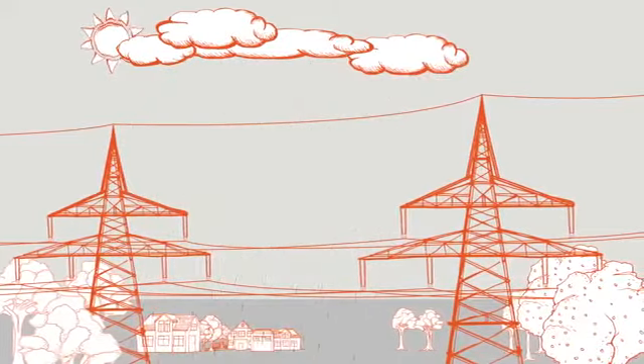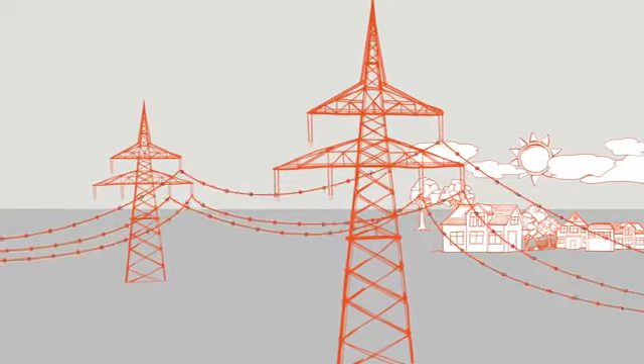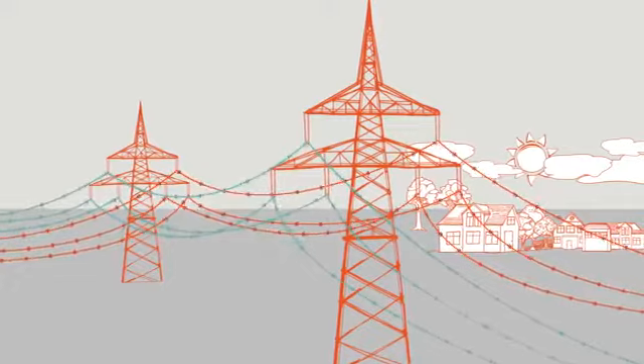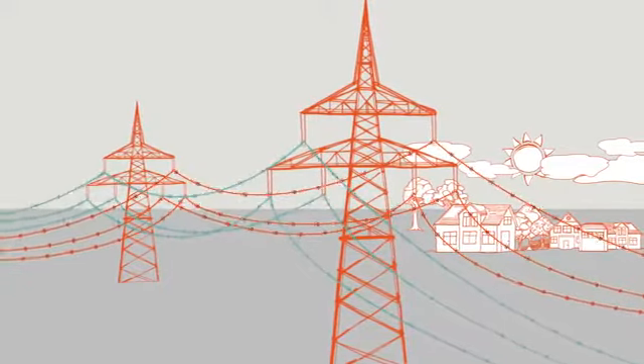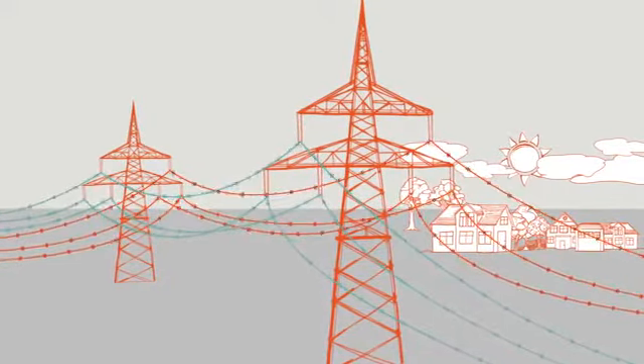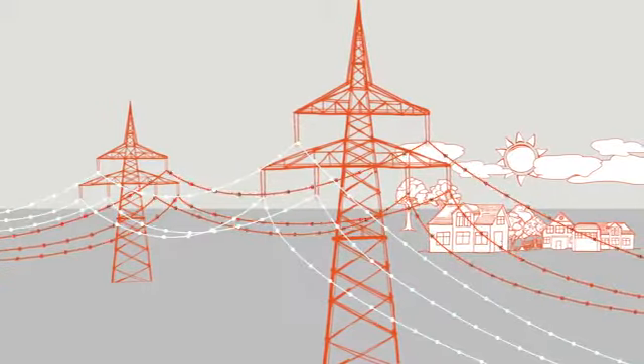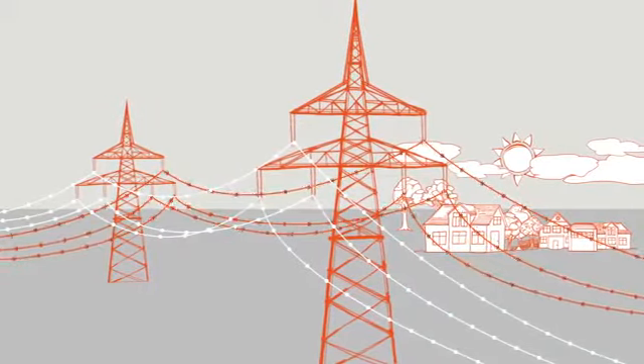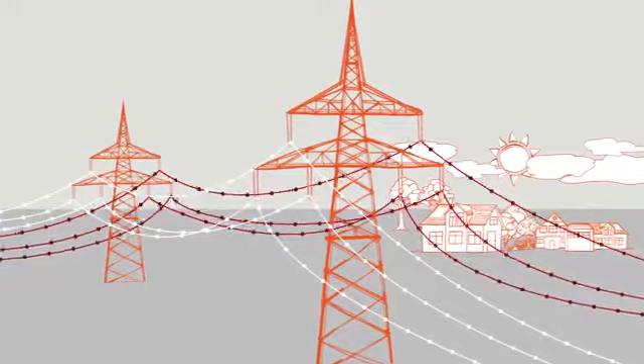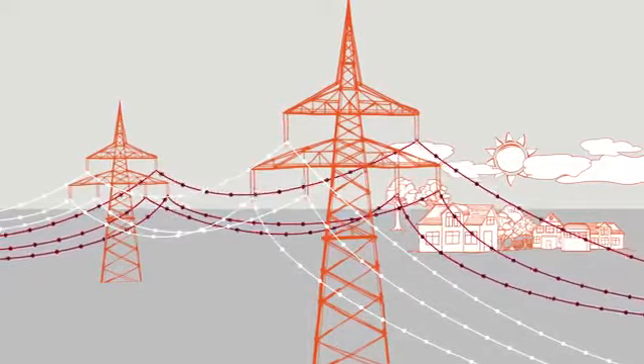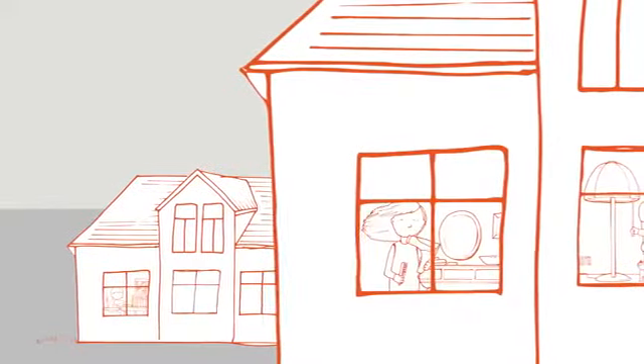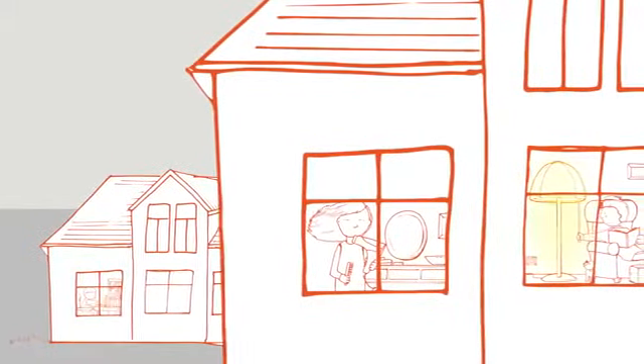The overhead lines of the 50 Hertz high-voltage grid are usually equipped with two electrical circuits. Electricity flows on the left and the right side. If one system or even the entire line fails, the rest of the power grid ensures the secure and uninterrupted electricity supply. This securing principle is called N-1.